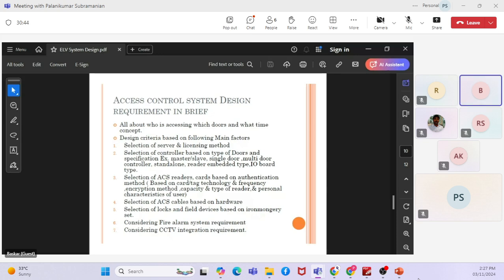Also, the type of the readers matters. We can have a keypad reader, or a reader only for the card, RFID card, or RFID card with the keypad, or with a thumb fingerprint reader, or based on eye impression, or facial recognition. There are different types of readers. So we have to choose the readers based on the specification and the client requirement. We should not choose equipment which is higher in value and not required. Let's say for a small storeroom, we should not use a face recognition reader, or for a server room, not use a standard RFID reader. We have to use the readers wisely and select them depending on the specification. If there are no specifications, sit with the client, understand the requirement, explain the security threats based on the type of the door, and choose the readers wisely.